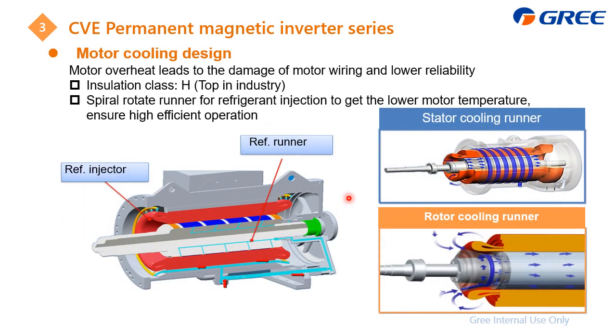And next is how we cool down the compressor. As you know, if we operate at a high RPM, inside it will generate a lot of heat. Here is how we cool it down. Inside it, we inject the refrigerant, and this liquid refrigerant will spray directly on the coils, and as it evaporates, it can absorb heat, which does the cooling and cools down the coil. And the motor itself is insulation class H, which is top in the industry. And also the spray rotate runner is for the refrigerant, injected to lower the motor temperature. This can ensure the efficiency.